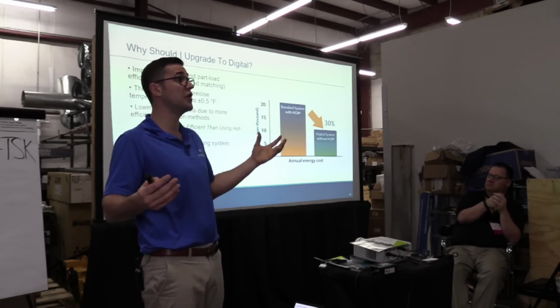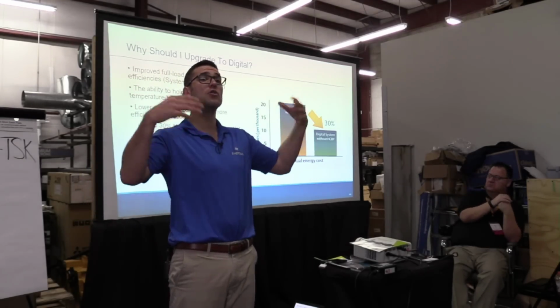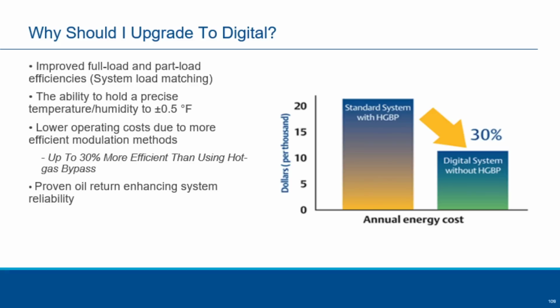Because if you're in an auditorium with 1,000 people, load's really high, you need that compressor to run. But everybody leaves, there's no body heat in that room anymore. Now that capacity dropped, right? So that compressor, what would happen to that system now if you didn't have some sort of capacity control? What would it do? No, it wouldn't flood back. It would short cycle, right? It'll turn on, turn off, turn on, turn off.